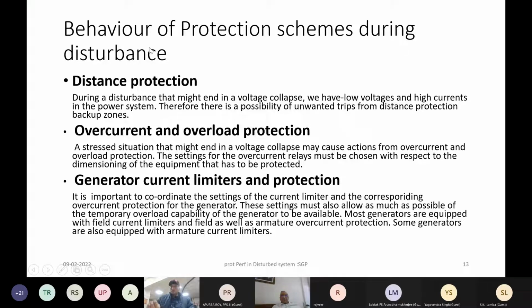Overcurrent and overload protection. Many times what happens is this: if the settings of overcurrent protection are not very well coordinated, the overload condition during the system disturbance due to voltage instability can result in the overcurrent relay operating in an undesirable manner. This was actually the cause of one of the recent disturbances in the western region, when even Bombay was affected with a power shutdown.